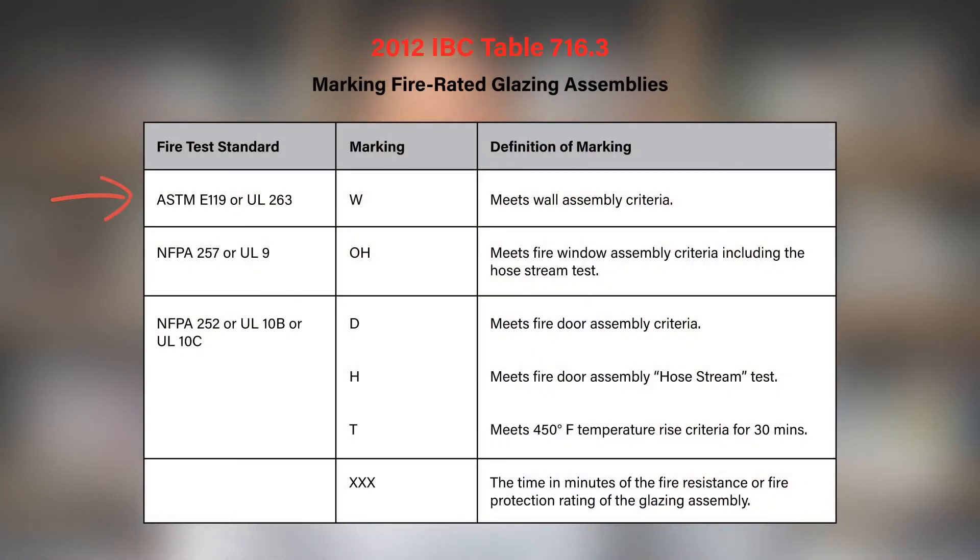The 2012 iteration of the IBC developed a marking system to communicate a level of performance, or the test standards to which each fire-rated product is tested. The 'W' indicates that a product is tested in accordance with ASTM E119, the wall standard. 'OH' indicates that a product has been tested to UL9 or NFPA 257, a fire-protected opening with hose stream.